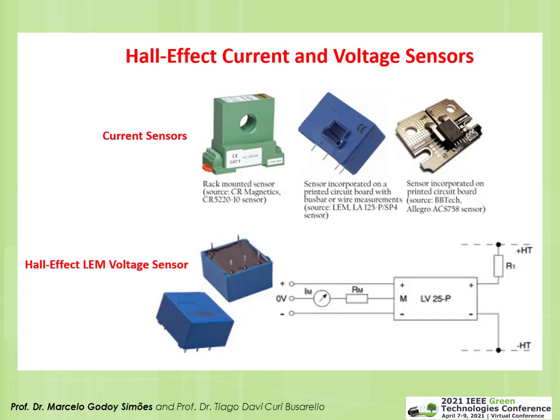LEM Hall effect sensors are widely used. The current sensor (on top) allows a wire to pass through a hole, or it can be embedded on a PCB. The LEM voltage sensor, model LV25-P, has a resistor in series; from terminals +HT and −HT (high voltage), and across Rm to ground, you get a voltage proportional to the high voltage that is galvanically isolated from the high-voltage terminals — very typical in motor drives and grid-connected inverters.